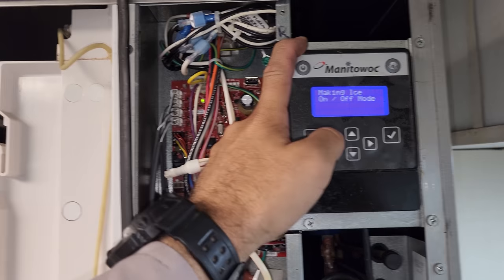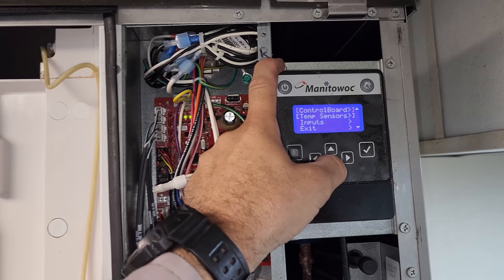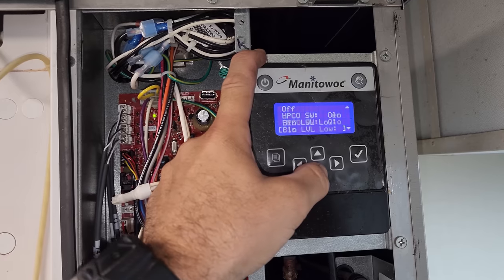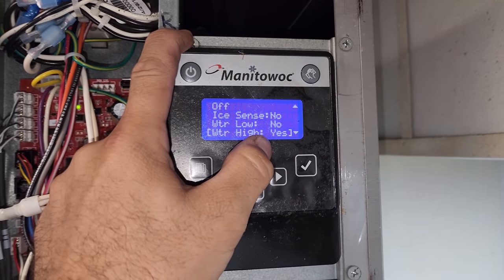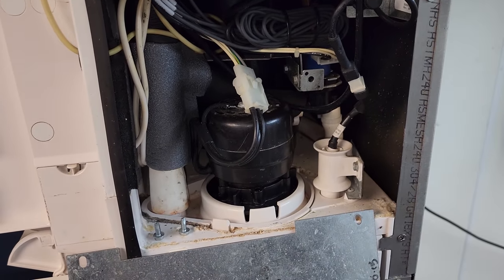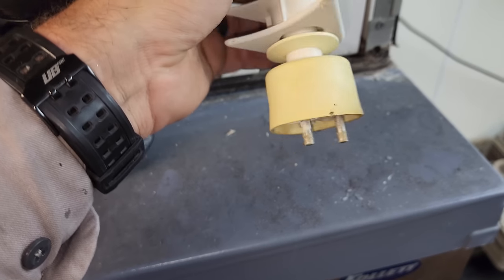Going to turn it off again. Service, diagnostics, inputs — curtain switch closed, high pressure closed, bin level. It's sensing water high, meaning it's sensing that water is high when it's not. So let's look at the sensor. I'm going to take out the water pump and pull the sensor out. The cleaners did a good job of cleaning the machine — look at that. It's ridiculous. I'm not even going to try to clean it. I'll just put a new water level probe in there.